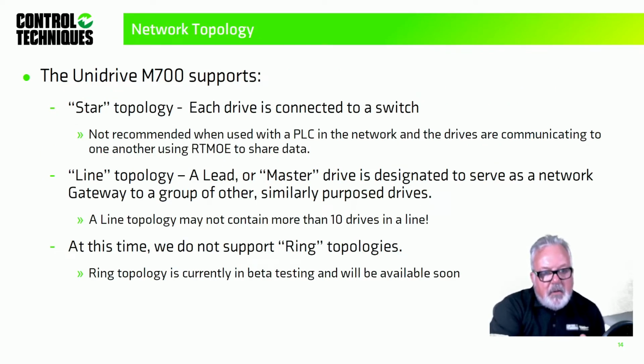So in terms of network design, our factory fit modules, not just the UniDrive M700, support a star topology, which is the classic Ethernet topology where every device has a path to the switch. So 4 drives, 4 patch cables, 4 ports on your network switch.